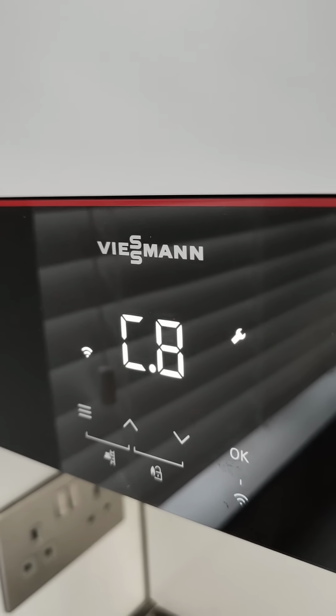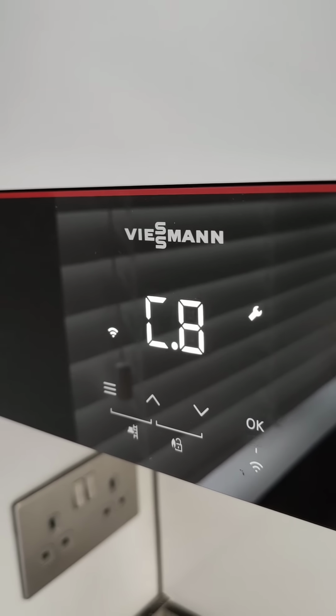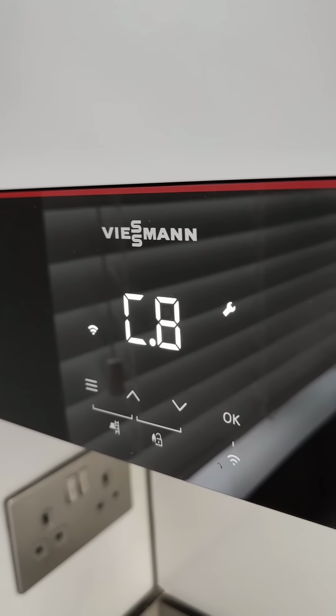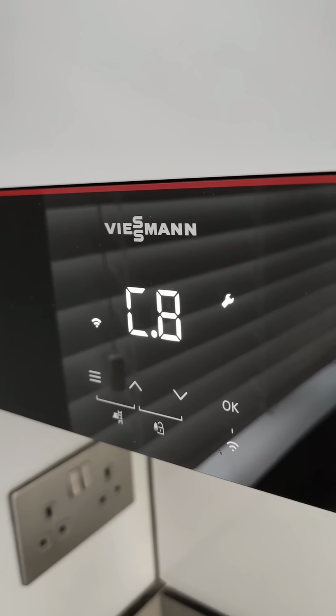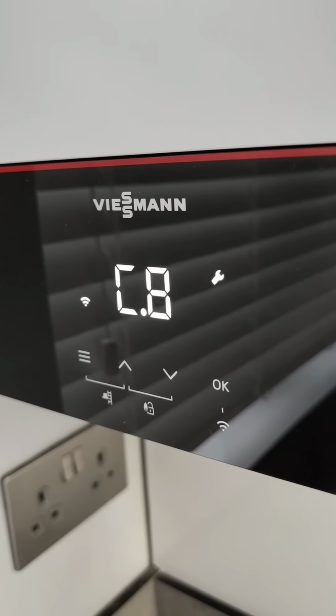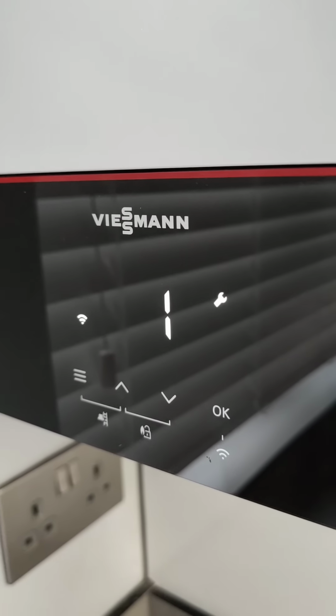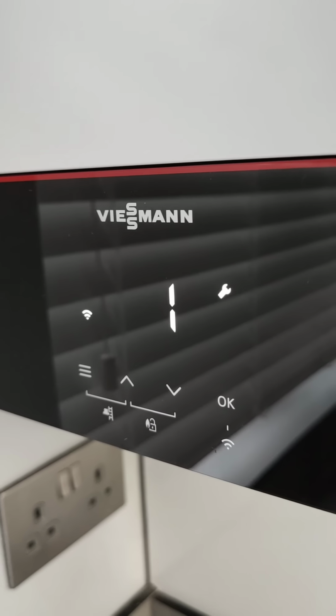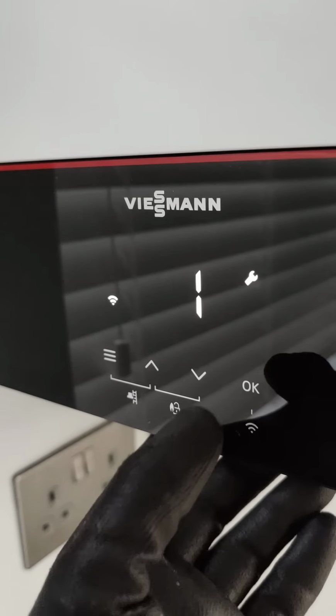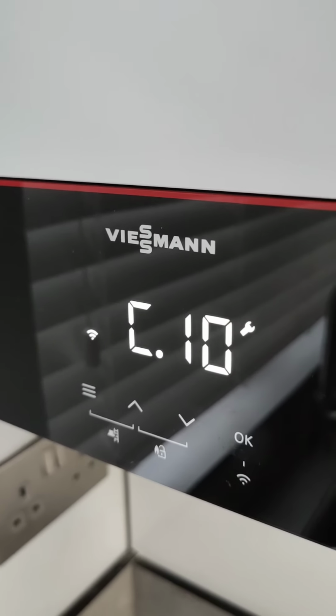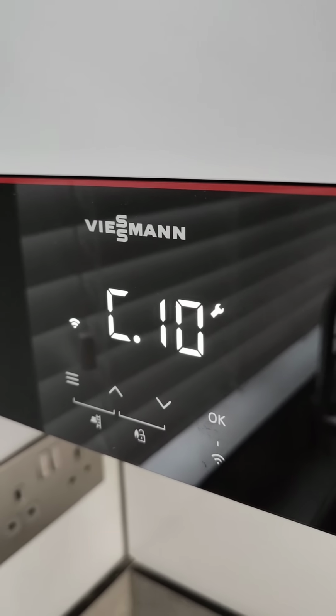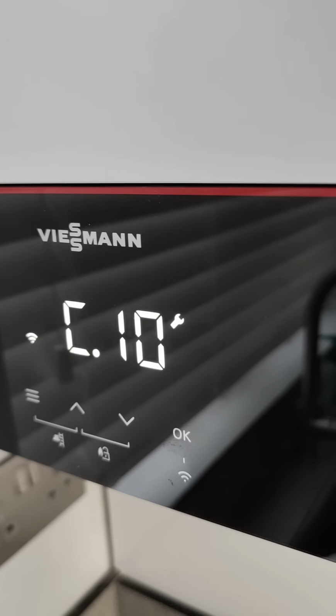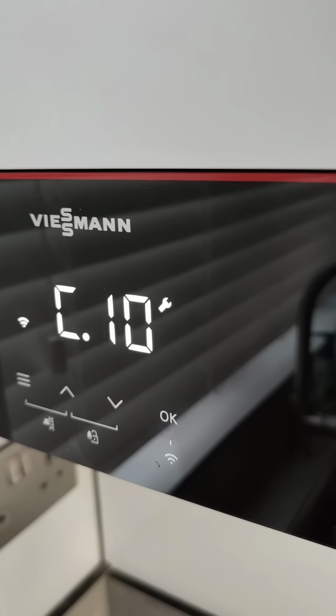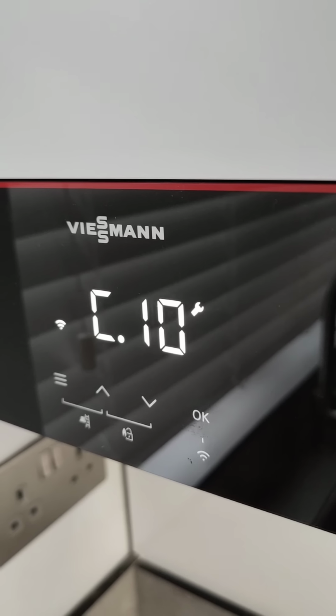Right, we need to use C8 if we're using a low loss header, or if we've got different heating zones, or if we're using mixed heating circuits. So we're just going to have this on number 1, which is just one zone with no low loss header. C10 is there's another plug inside the boiler. We can plug into different things so we can tell the boiler what that plug is actually doing.